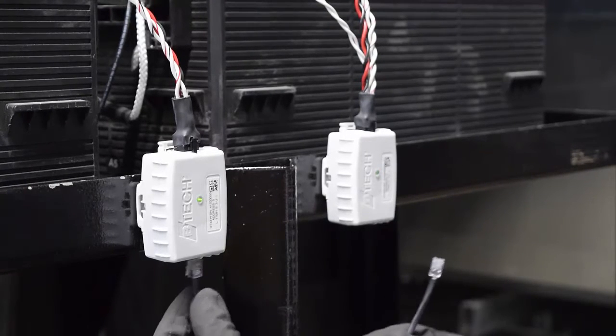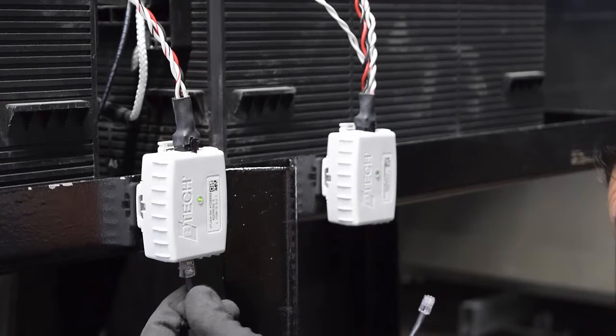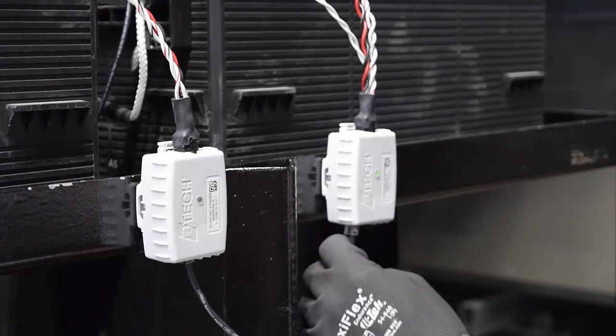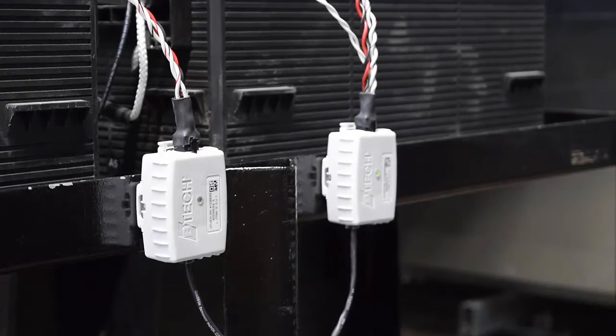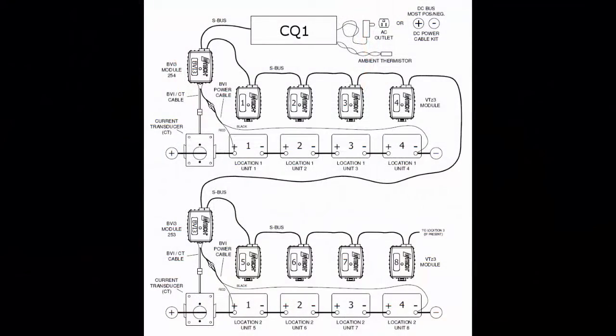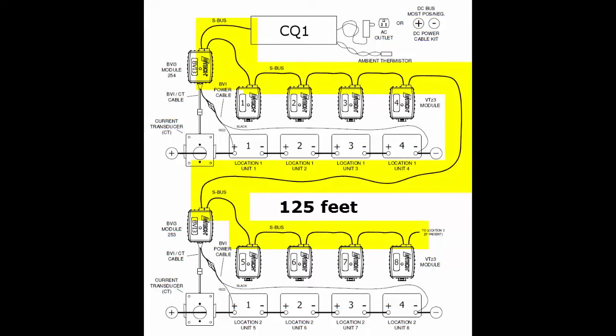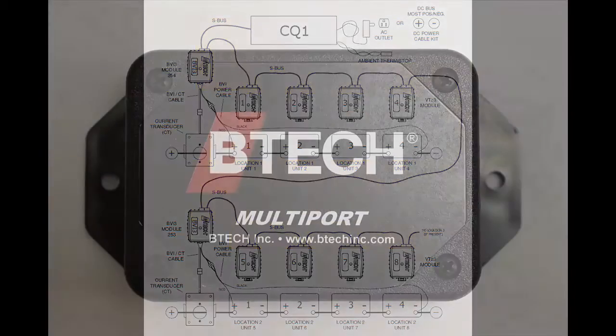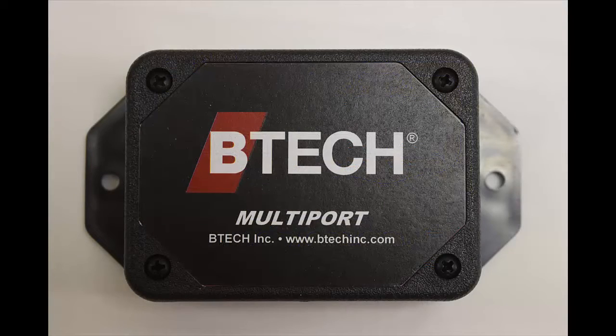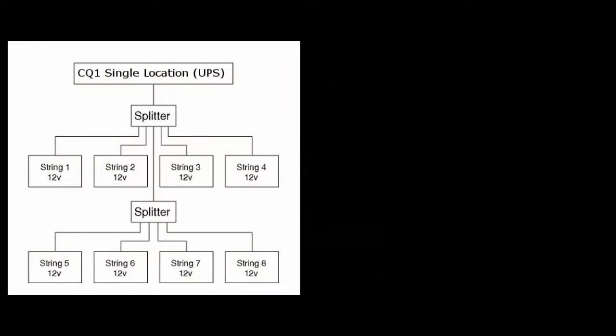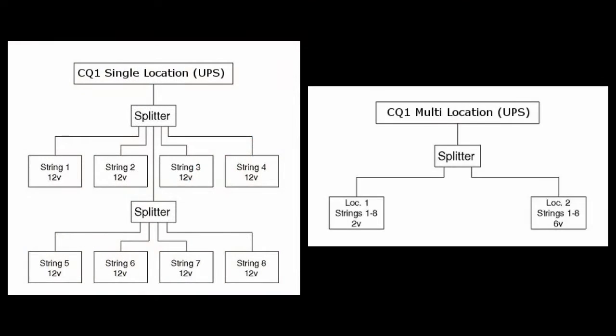Make sure there's enough slack in each S-Bus connection so there's no tension on any of the connections. Use the shortest S-Bus cables necessary between modules to minimize overall cable length. The maximum S-Bus run from the controller to the last module is 125 feet. You might have an S-Bus splitter module which allows the S-Bus to split up for up to 5 S-Bus runs. Here are two examples of an S-Bus splitter usage.